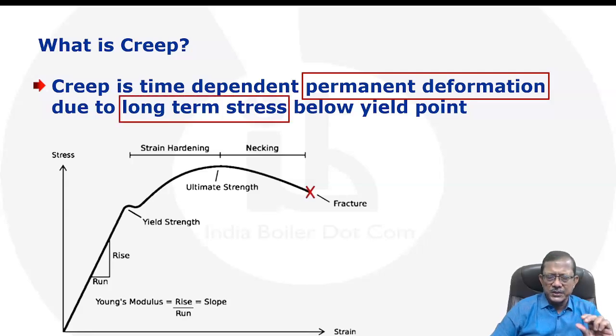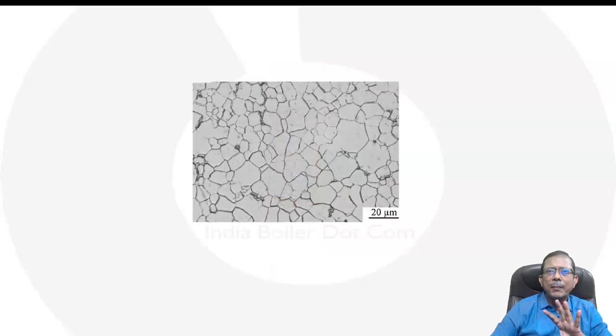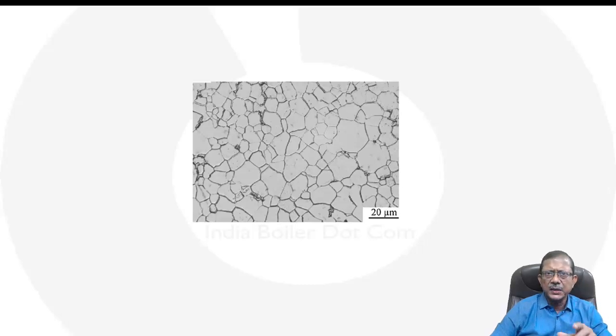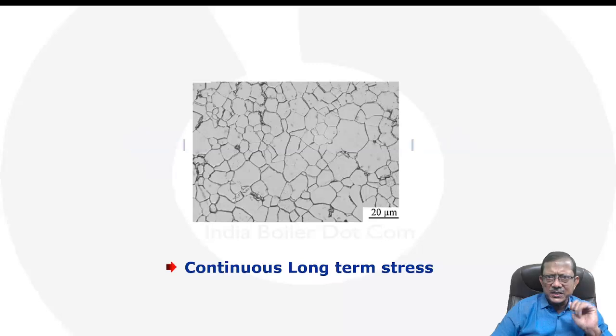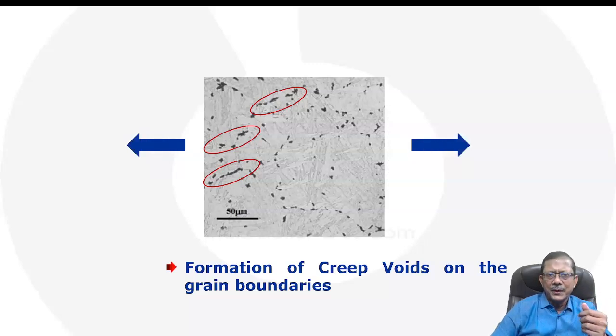If we take a very close look at a tube component — using an electron microscope scan — we find that the tube metal is made of multiple grain structures. These grains are connected with grain boundaries, and these grain boundaries are the weak points. When this tube is working long-term under continuous stress, certain permanent voids occur between the grain boundaries — intergranular voids. When the stress is removed, these voids will remain.